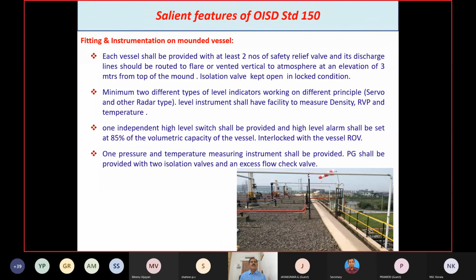Fitting, and each vessel shall be provided with at least 2 numbers of safety relief valves, and its discharge line should be routed to flare or vented vertically to atmosphere at an elevation of 3 meters from the top of the mound. So the 2 safety relief valves should be provided, and the outlet should be routed to flare. If flare is not available, it should be vented vertically to atmosphere at an elevation of 3 meters from the top of the mound. So the isolation valve of the SRV should always be kept open in locked condition.